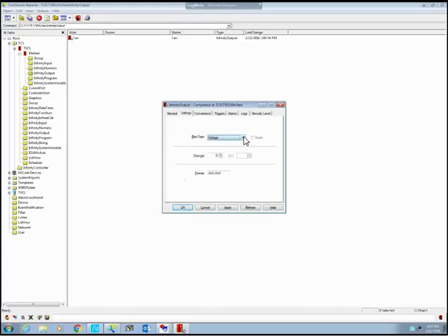Settings, I'm going to make this a digital point because it's still the same controller. I'm going to put this on channel 2. Again, I'm going to make this on and off point. And if I wanted to log it, I could. We'll go 24 hours on average at 1 hour apiece.